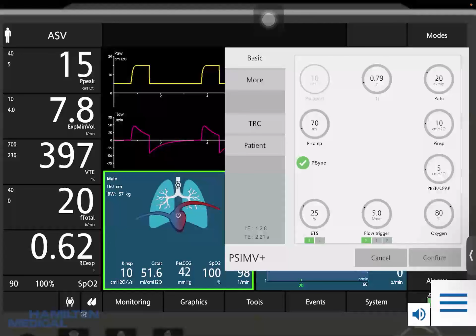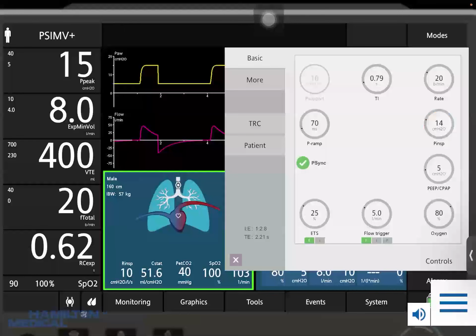So one thing is we have to see. I can't demonstrate here because the simulation is not supported for active patients. So let's see. We have to see both things. I mean, assisted control as well as the supported breaths. So if the assisted breaths deliver a lesser volume, we have to increase this peak inspiratory pressure, keeping in a safe limit. All right. If you see supported breaths deliver less tidal volume, you have to increase this pressure support. So the top left hand corner, you can see the pressure support. So we have to see both pressures to achieve the set tidal volume delivered in both phases.